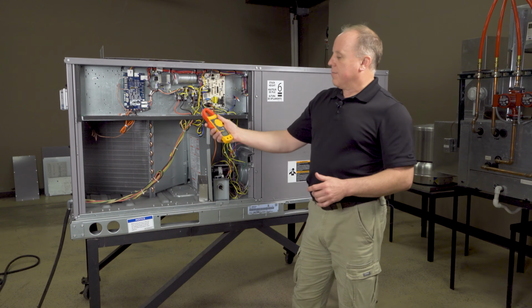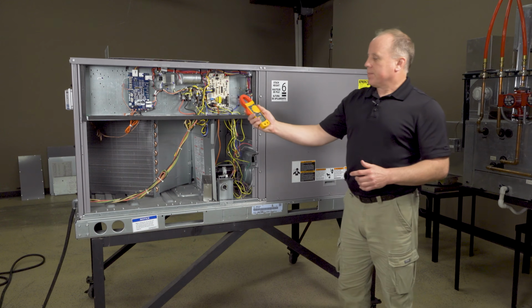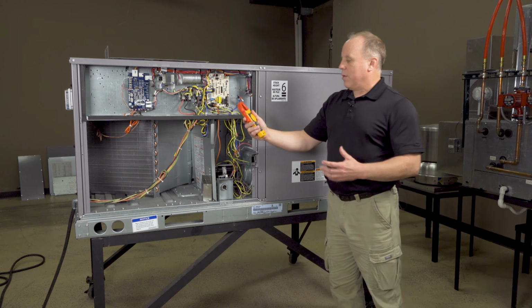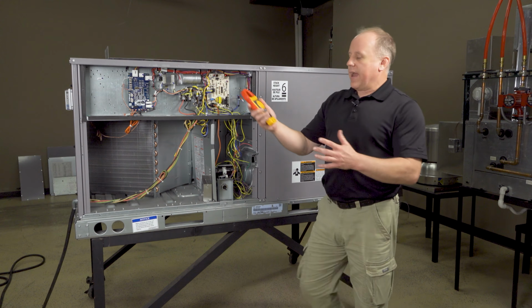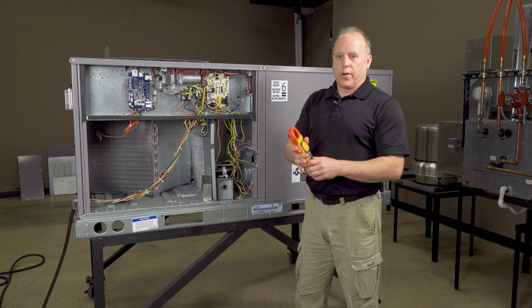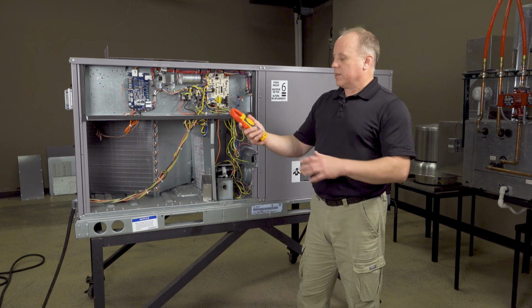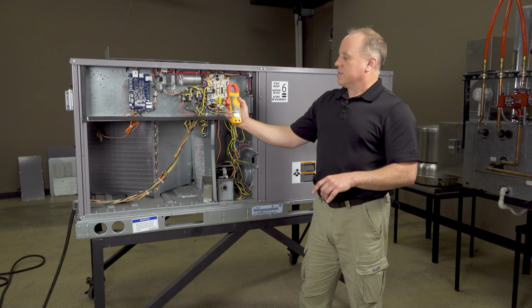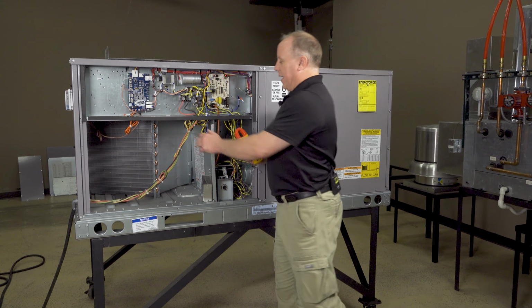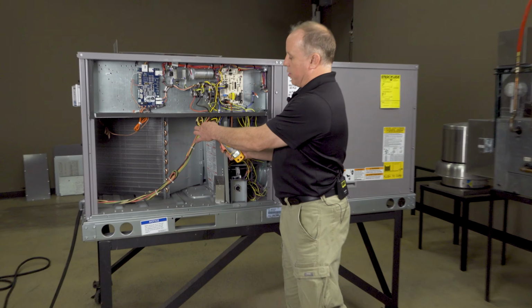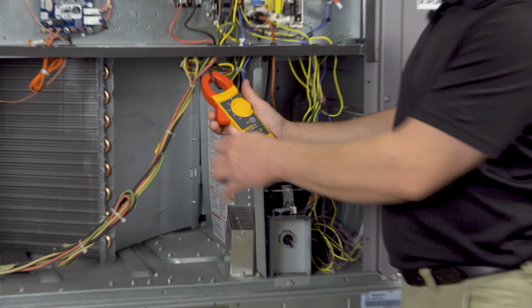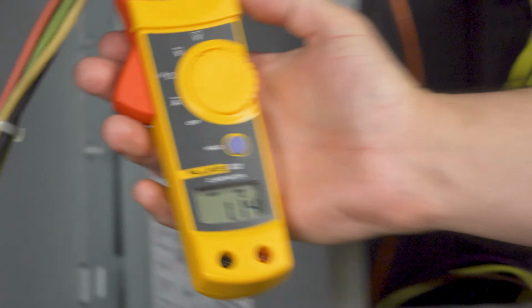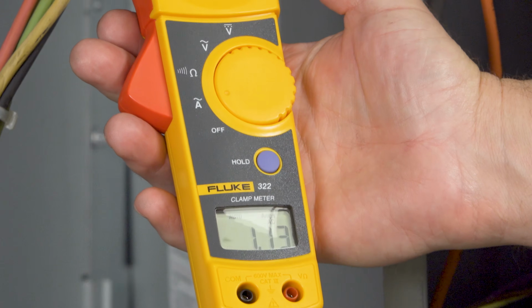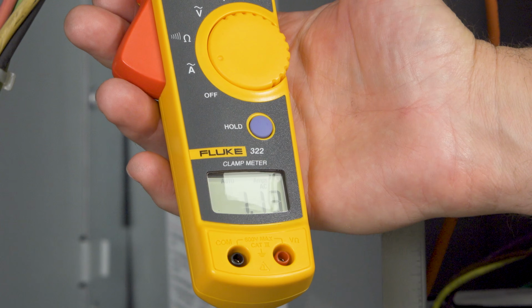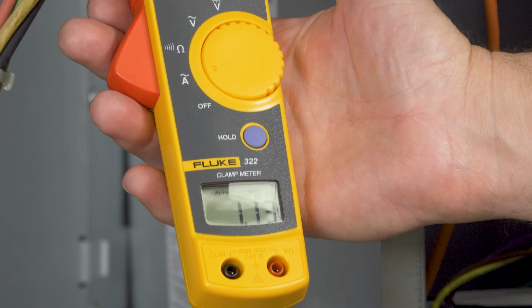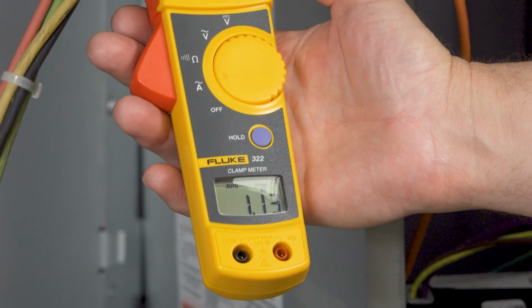So I'm going to get my amp probe. I'm going to get that out. Most multimeters now are amp clamps, and they do regular voltage and other readings. So I'm going to get this clamp meter, set it to amps, and I'm going to get on one of the wires from the motor, the black, which is going to be one of our power leads. I'm going to get that reading, and right now we're reading 1.14, 1.13, and it's going to be holding right in there.